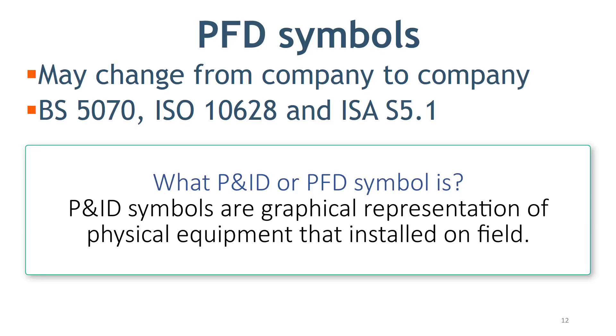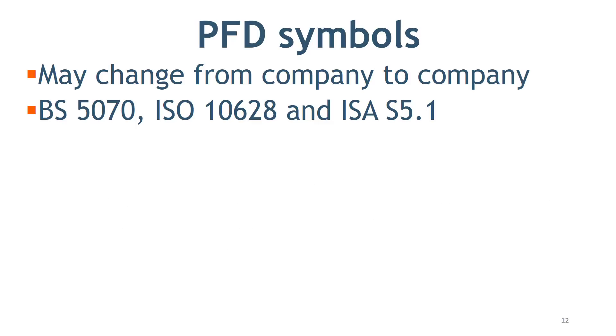What is a P&ID or PFD symbol? P&ID symbols are graphical representations of physical equipment installed in the field. There are a few ISO and British standards available that provide symbols and best practices to draw PFD and P&ID, such as ISA S5.1, BS 5070, and ISO 10628.